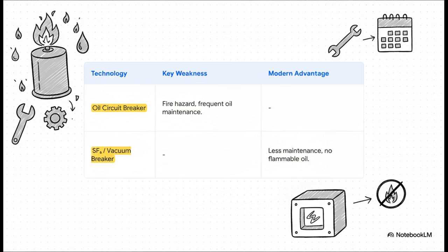And this is really where modern technology just leapfrogged the old OCB. Newer breakers use things like SF6 gas, which is non-flammable and an amazing insulator, or they put the contacts in a total vacuum, where an arc literally can't even form. Both of those options are way safer, smaller, and need a whole lot less maintenance.